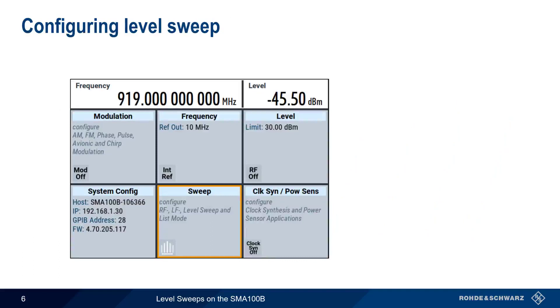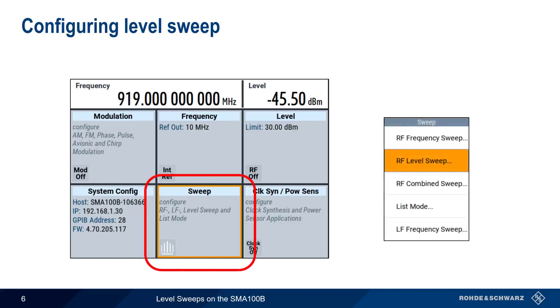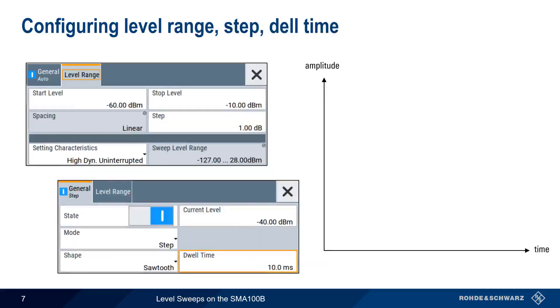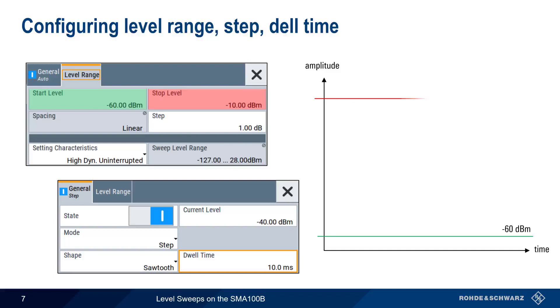Let's go step by step and explain how these are configured on the SMA100B. We start by tapping on the sweep tile and then choose RF level sweep from the list of available sweep types. The most basic parameters of a level sweep are the start and stop levels, which are configured under the level range tab. In this example, we configure the sweep to start at minus 60 dBm and stop at minus 10 dBm.